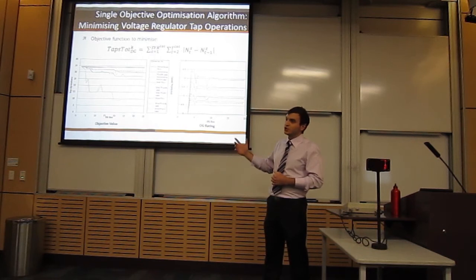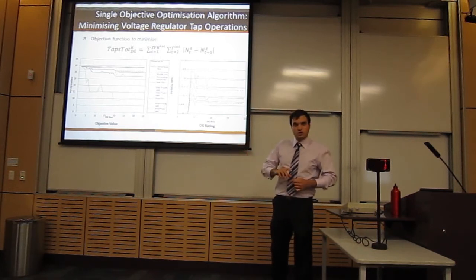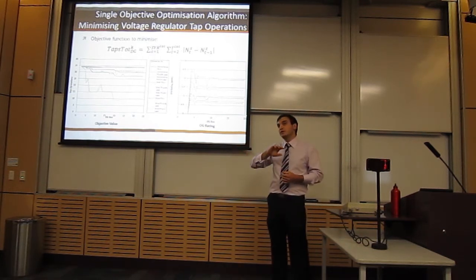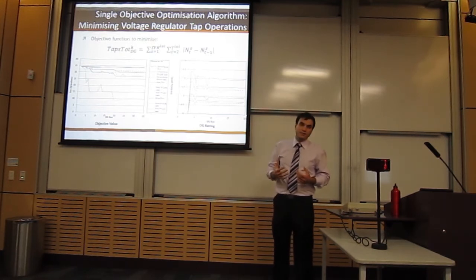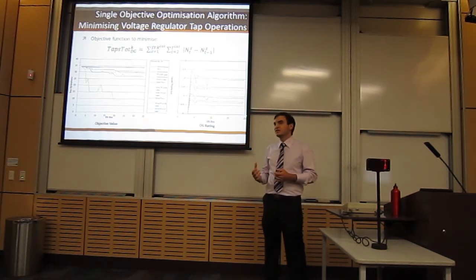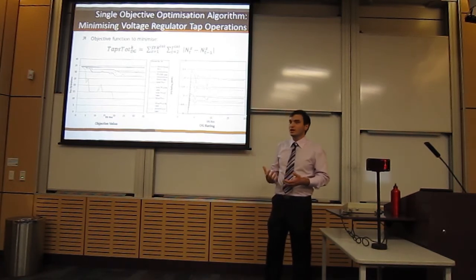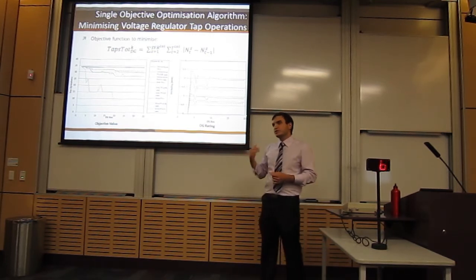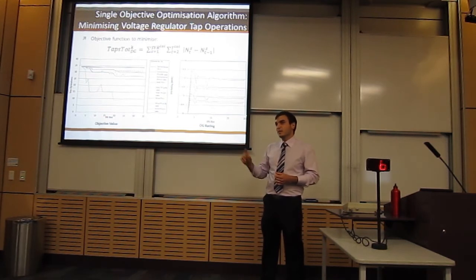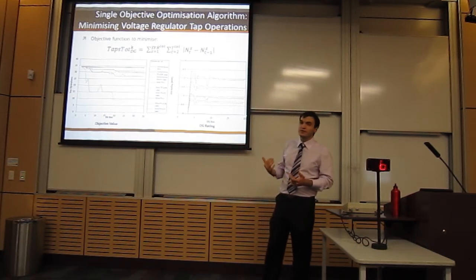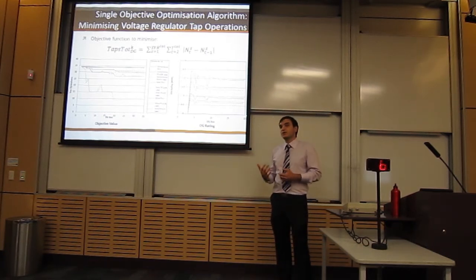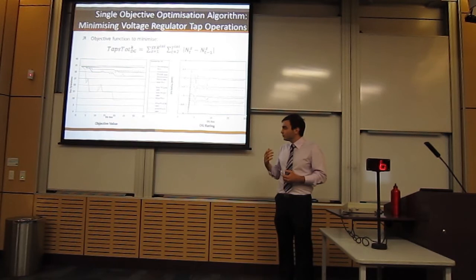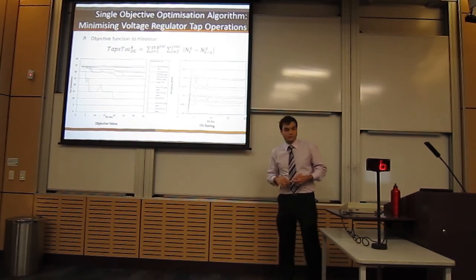This reduction was most prominent when solar generation was implemented. This is because in the middle of the day when load demand peaks, solar generation roughly follows the same trend. Therefore, the voltage at the nodes does not change significantly, and the voltage regulators do not have to operate. As seen on the right graph, the optimal DG size remains fairly consistent regardless of the bus it's implemented on, so it is more efficient to implement on the bus where the greatest reduction in tap operations is present.